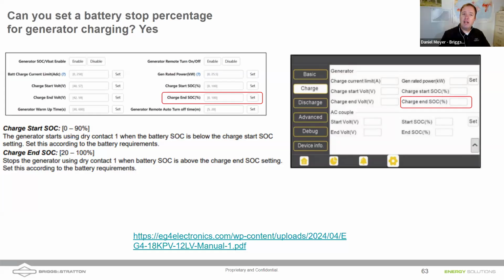With EG4, they have the ability to set the end state of charge for a generator run cycle. And here's my example. Let's say it's evening. The batteries are low. The batteries aren't going to make it through the night. Let's go ahead and start up that generator. Let's maybe get the batteries up to, say, a 50% state of charge, and then shut the generator off. I don't need to run the generator into the wee hours of the night to get a full charge, because I know in the morning the sun is going to come up and fully charge those batteries back up again. So that's a small thing, but I think a very powerful thing is the ability to not only start a generator based on a state of charge, but also stop a generator based on a certain state of charge. And again, it is available through Solar, though you just have to do it a little bit differently through time of use settings.